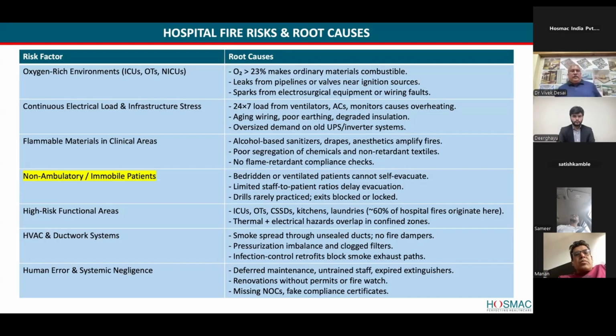Okay. Then the last point here is human error and system negligence. This is happening because we defer maintenance. It's a very common practice, even in our offices, probably we don't do it. There is untrained staff, we don't take cognizance that people need to be trained. The extinguishers are past their expiry date, so again, it's a human error. Renovations without permits or fire watch. So what Satish was explaining, that if you are doing some renovation, then you have to take care of the AHU, fire dampers, smoke exhaust systems, and the fresh air to be brought in during these things. All these things need to be done.